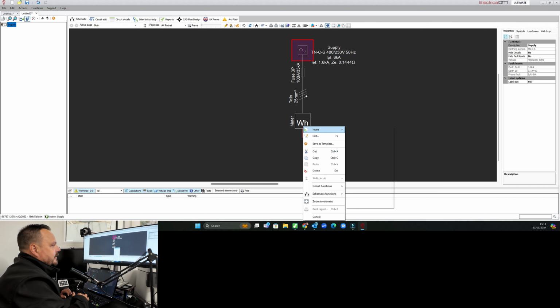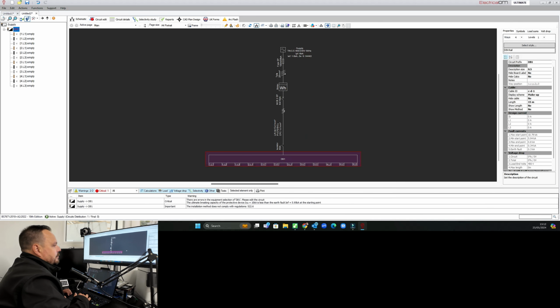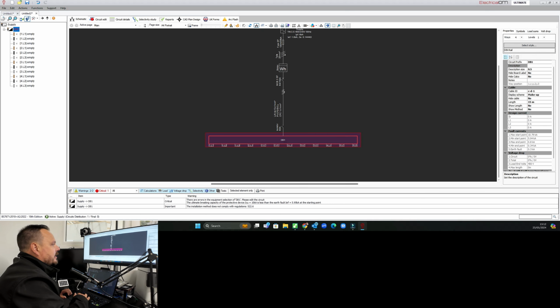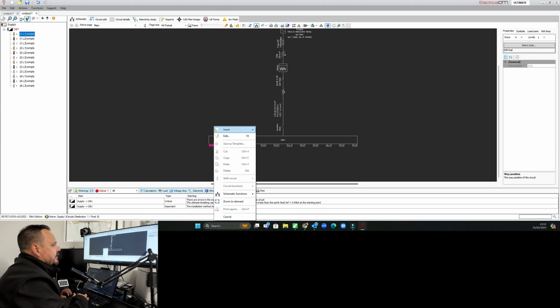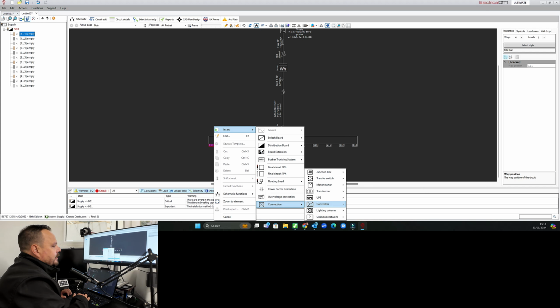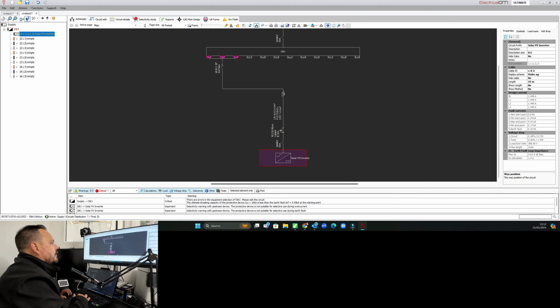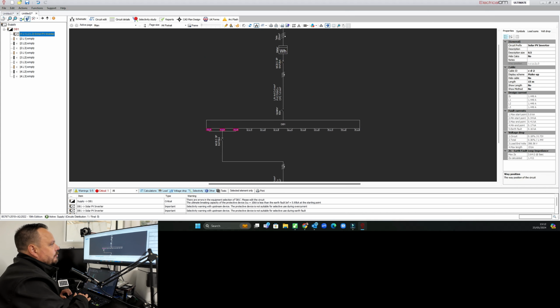So again, we right click, insert, and choose a distribution board, three-phase. So that's popped straight in there. It's using a four-way board, which is handy because that is what we are utilizing. So with this, if we right click and say what we're going to insert in this case, we could have a connection, for example, a converter, a three-phase solar PV inverter, which we're going to put into way one. Now you can see it pre-populates that with lots of different bits and pieces, and we've also got some pre-populated stuff leading down to our distribution board.